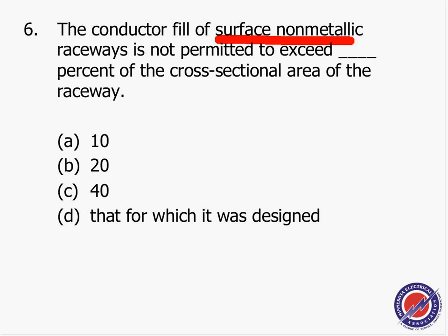Surface nonmetallic raceway is not permitted to exceed percentage of cross-sectional area. You know, a lot of you guys get this wrong for one reason, because I believe you were confused between the wireways and the surface raceways. If it was a wireway, then 20%. You can't fill more than 20%. But because it's a non-metallic raceway, it's not a wireway. So then there is no limit. The limit is by how much the manufacturers want you to limit them.